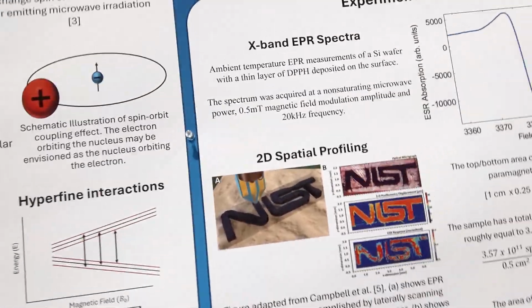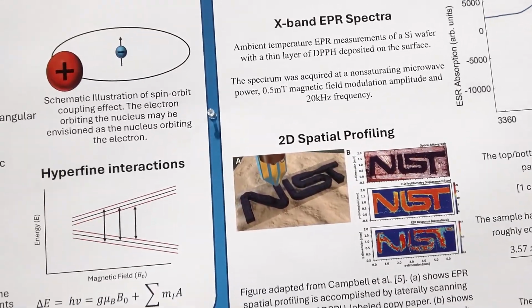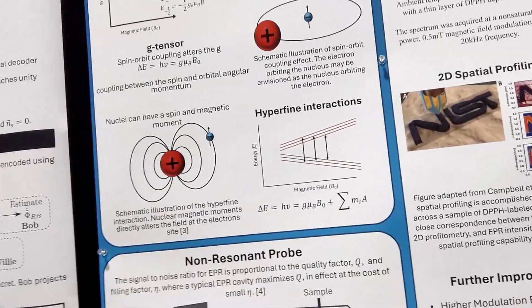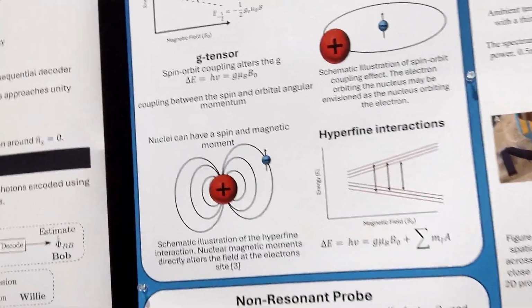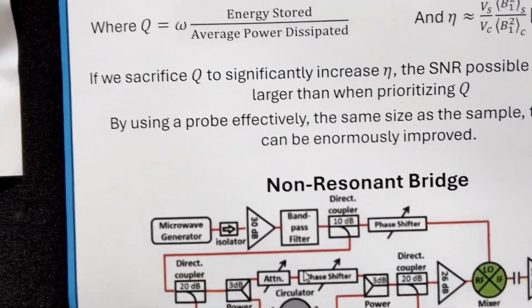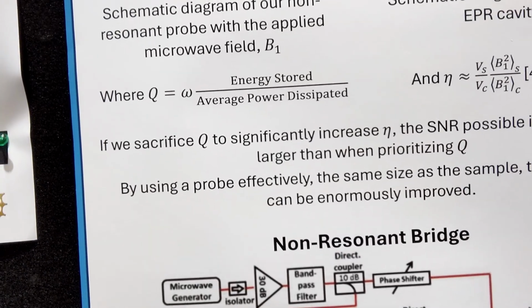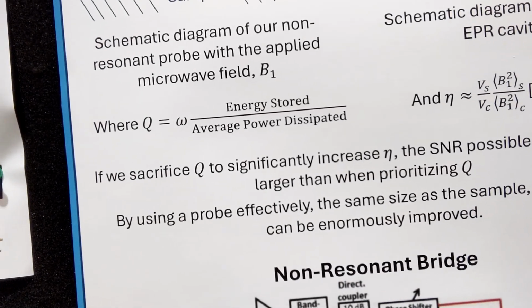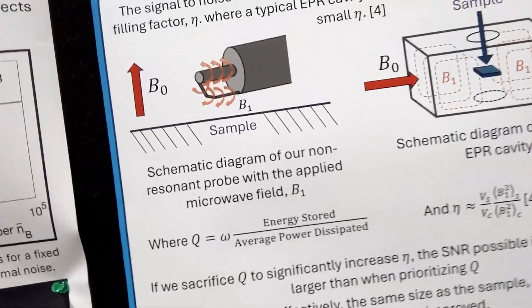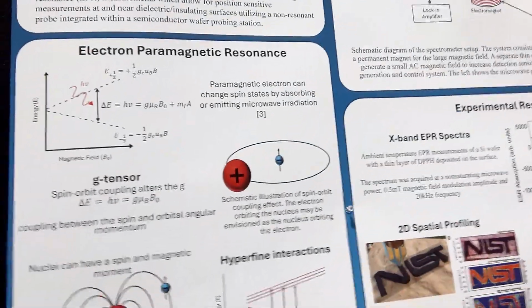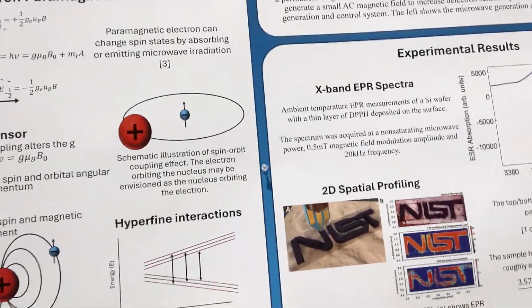And the small non-resonant probe loses all of its what we call quality factor, which is the amount of energy stored over the average power that is dissipated. But what we get instead with the small probe is a major increase in filling factor greater than the loss of our quality factor. And the filling factor is essentially the amount of microwave energy that our probe creates that ends up stored in the sample. And so by using that trade-off there, then we actually get an increase in sensitivity over standard EPR using a cavity. And then from there, we did an experiment to see, so then what is our sensitivity?